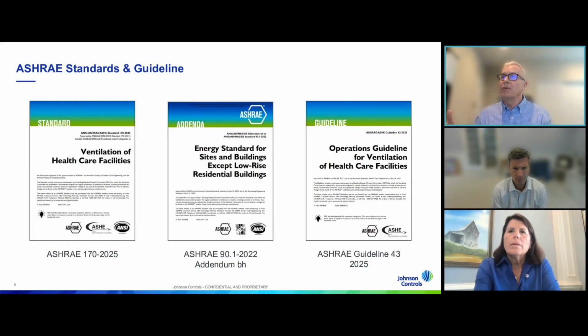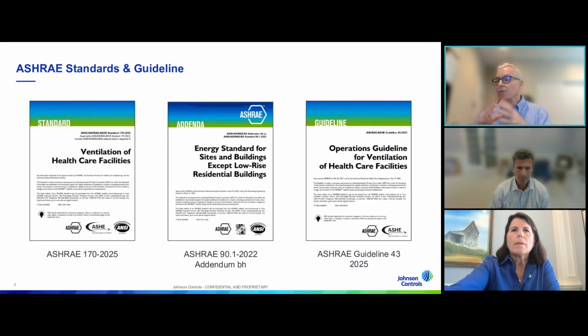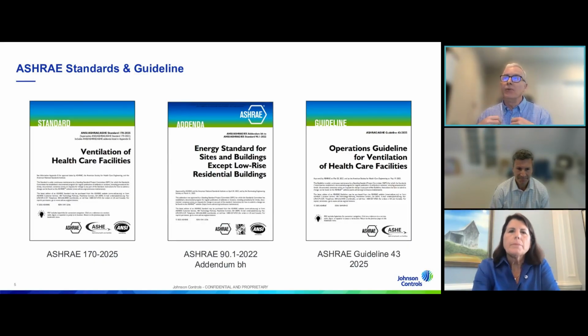Then the one on the right there is a relatively new guideline as well, ASHRAE Guideline 43. That's really pointing back at 170 and saying, okay, how do we have to operate our hospitals so that we can achieve 170, and not just achieve it, but have that resiliency built into it and have that continuous operation? That really expands not just to the rooms themselves, but to the equipment that's supporting those rooms. What do we need to do for the air handling units to make sure that they're maintained and they're not going to have an issue or a fault? What are we doing with the chillers and things like that?